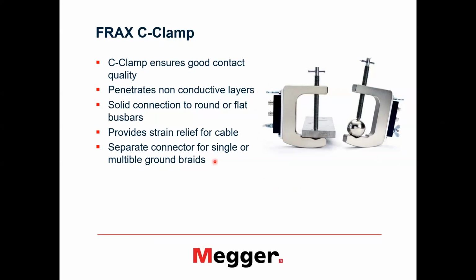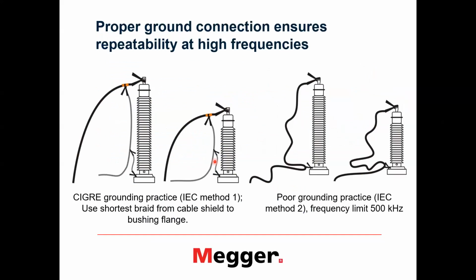So the clamps are one thing to ensure good contact. Another thing is to make proper shield grounding. In CIGRE and IEC standards, one has come to agreement that the shield grounding has to be done in a straight line along the bushing surface, as short as possible and as straight as possible. This is in order to avoid strange behavior at high frequencies. For example, loops like this will not allow you to make good repeatable measurements when you come next time and make another type of loop.